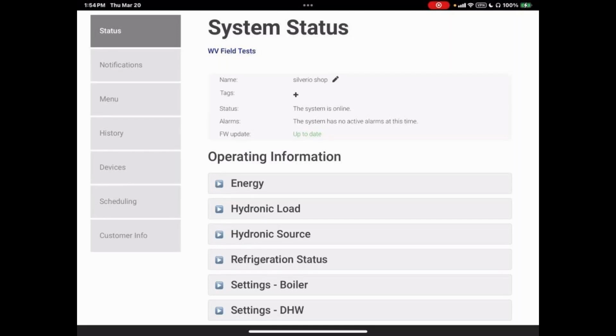And absolutely, if you're controlling those with some kind of external control, an HBX or a Tecmar, that could have some type of setting where you might have a priority, and some kind of priority override function. You use the term horsepower, and it really does come down to that. We've literally seen residential projects where domestic water demand is over 500,000 BTUs per hour, and if you ask a client like that, "How long do you want to sustain that?" they'll say, "As long as I want the faucet on." They don't want to run out regardless. They don't want time limits. So it's a good sales opportunity to build a nice multi heat pump system.